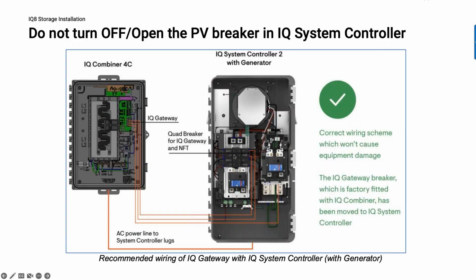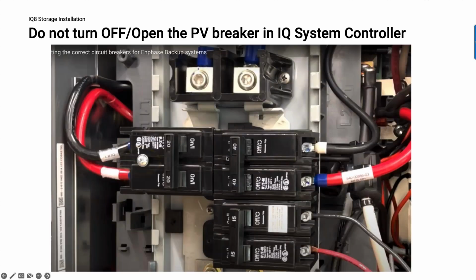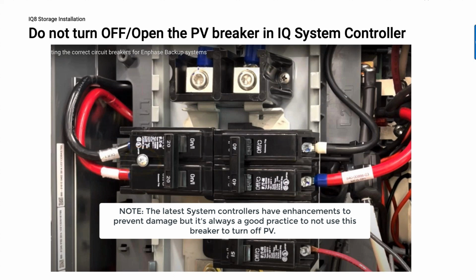When you are turning PV off, all right, in a configuration where you have IQ8s into the combiner box, and then the IQ gateway is powered off the system bus here, or the common bus. If you want to turn PV off, you should never turn the PV off from the PV breaker. All right, that's this breaker in the system controller. There is a breaker here, and that breaker is for PV, but you don't want to disconnect PV from this breaker. If you ever want to de-energize PV from the system, do not do it from this breaker. Doing this will create a voltage anomaly that could damage the system controller.